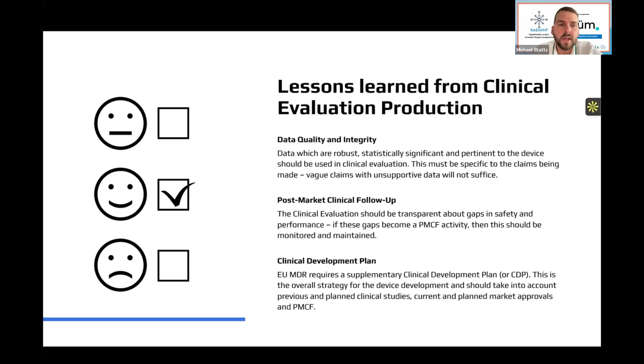The other thing to note is that whilst we're here to specifically talk about clinical evaluation, which is demonstrating clinical safety, this is just one of essentially three parts of the overall conformity statement that you would submit to the regulator. The other is the technical file, which demonstrates technical safety, and then your quality management system, your ISO 13485 system, which demonstrates operational safety. So this is just one of three elements to your overall safety and compliance evidencing, but just wanted to highlight that.